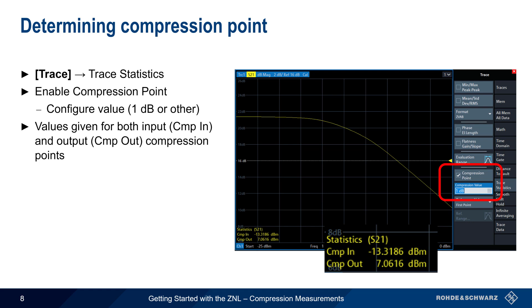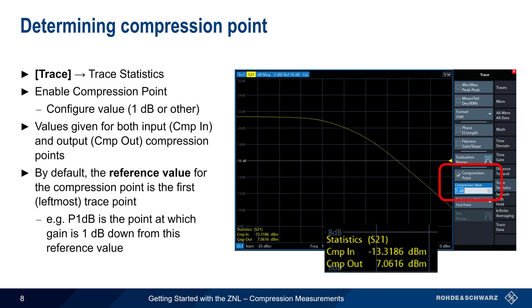In addition, the ZNL can automatically calculate compression points from this trace. This is done by pressing the Trace hard key, selecting Trace Statistics, and then enabling the compression point measurement. The default measurement is for 1 dB, but this can be modified by the user. Once enabled, the compression point measurement automatically calculates both input and output compression points and displays them on the screen. In the default operating mode, the reference value for the compression point calculation is the first or leftmost point on the trace. P1dB is calculated by finding the point at which gain is 1 dB lower than this default reference value.